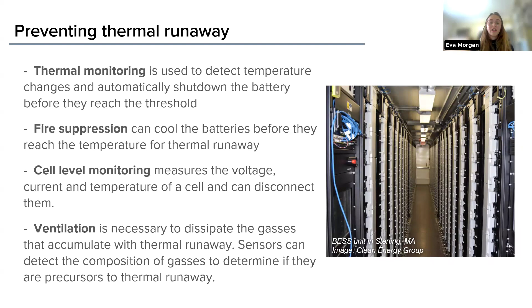There have been a lot of improvements in thermal runaway prevention in the past decade or so. There's thermal monitoring, used to detect temperature changes within the battery and automatically shut down batteries. There's fire suppression, which can cool those batteries before they reach the temperature threshold for thermal runaway. There's cell level monitoring, which can measure voltage, temperature, and current of the cell, and can also disconnect each battery cell. Ventilation is a very important step to dissipate gases that can accumulate during thermal runaway, and there are sensors that can detect the composition of those gases. All of these things are automatic, and a good battery installation will have all of these monitoring and suppression devices, which are also mandated in a lot of the certifications and fire codes we mentioned before.